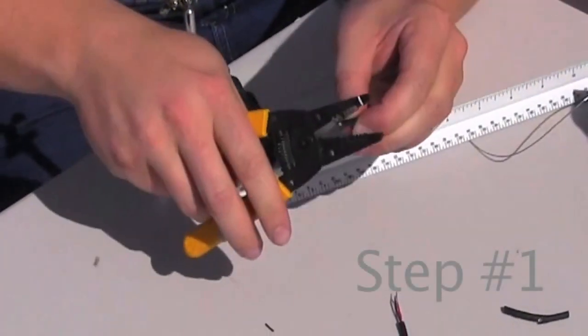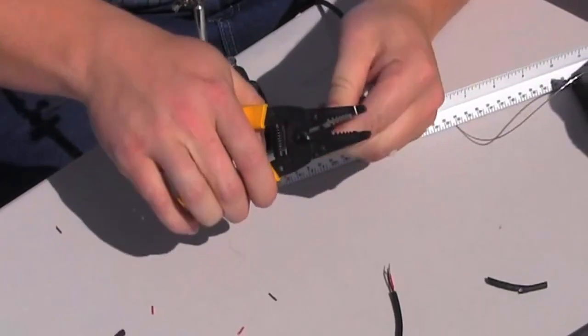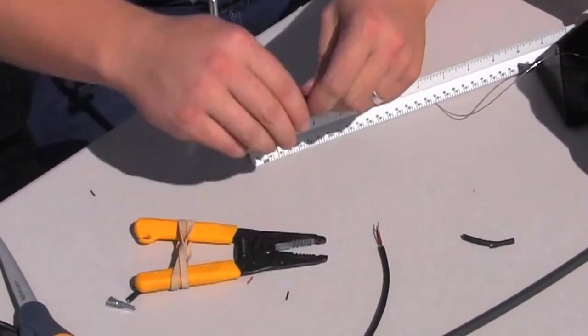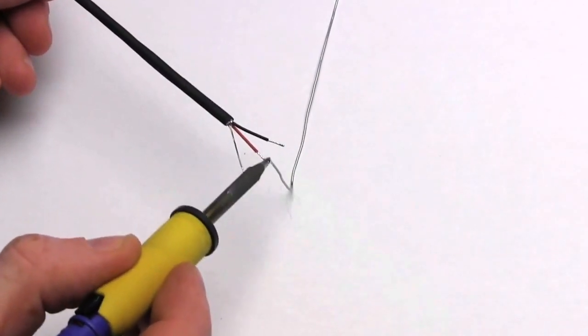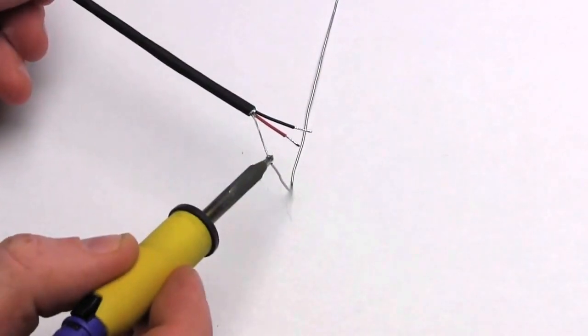Step 1: strip the outer cable insulation 5/8 of an inch while stripping and tinning the individual wires 1/4 of an inch. Note that tinning the individual lead wires helps to eliminate cold solder joints by cleaning the individual strands and allowing solder to flow more freely.